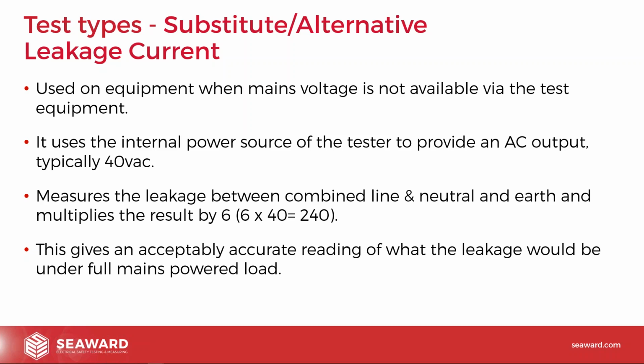So the substitute alternative test is a test we can do, but it does it at an extra low voltage, a much lower voltage. Typically it does this at 40 volts AC. So we put 40 volts AC into the equipment, between the line and neutral joined together and the protective conductor, or for class 2 equipment, the line and neutral joined together and exposed surfaces, pretty much like the leakage test or the touch current tests. Then it measures the leakage at that voltage and scales it up. So for example, if it saw 1 milliamp at 40 volts, it would scale that up, effectively times it by 6. So what would it be at 230, 240 volts? We presume that we'd see 6 milliamps if we got up to there. So there's a scaling going on in that process to get to a simulated result.